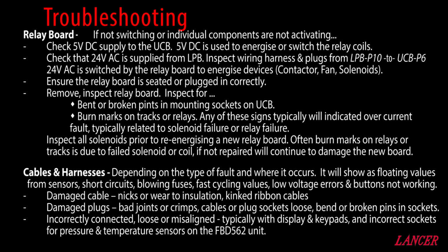Cable and harness faults, depending on where they occur, will show us floating values from sensors, short circuits, blowing fuses, fast cycling values, low voltage errors, and buttons not working. These are typically due to nicks or wear in the insulation or kinked ribbon cables, damaged plugs which have bad joints or poor crimping, or the cables and plugs are loose and have bent or broken pins, or are incorrectly connected, loose or misaligned. This is typical with displays and keyboards, and incorrect sockets for pressure sensors and temperature sensors, particularly in the FBD 56X range.